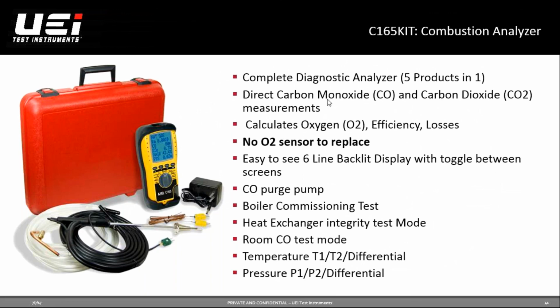But we put in a CO purge pump. When it sees high levels of CO, it shuts off the main pump and turns on a secondary pump that pushes all that CO out of the unit, so it never touches it. Remember, oxygen sensors can get expensive to replace, and CO sensors can too. So we've effectively removed the possibility of two sensors going bad, since we don't have an oxygen sensor and we have that CO purge pump.